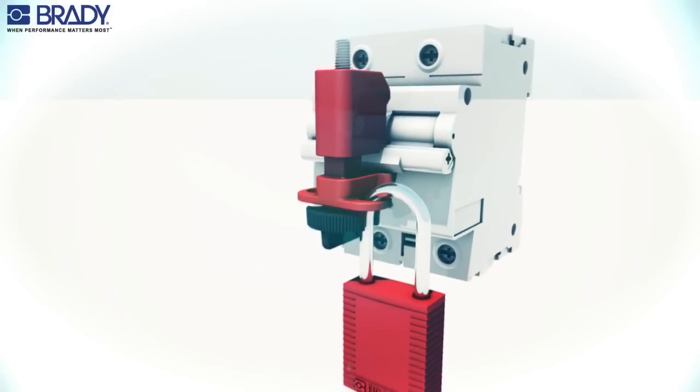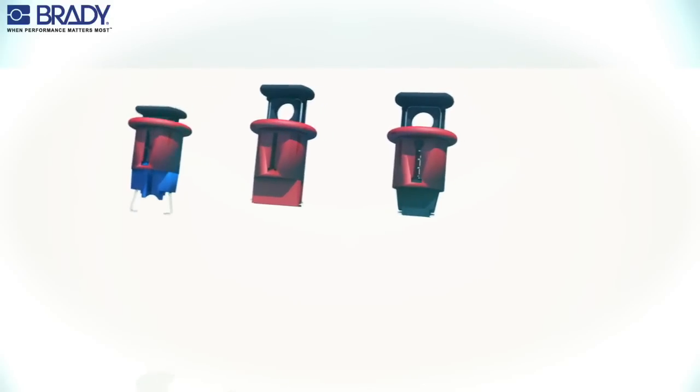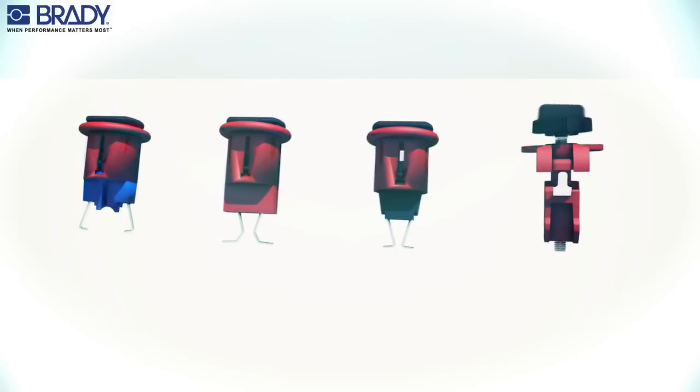Insert the padlock through the hole to secure the device in the locked position. For single pole breakers, use either the pin in device or one of the two pin out devices. For multi pole breakers, the tie bar solution is recommended.